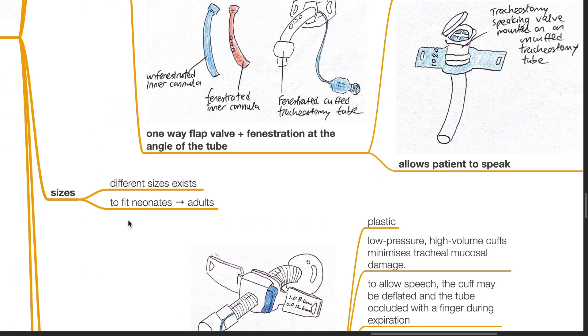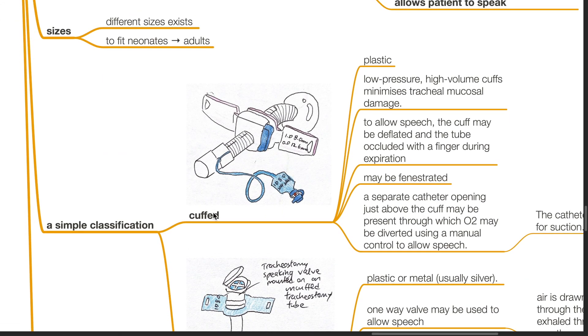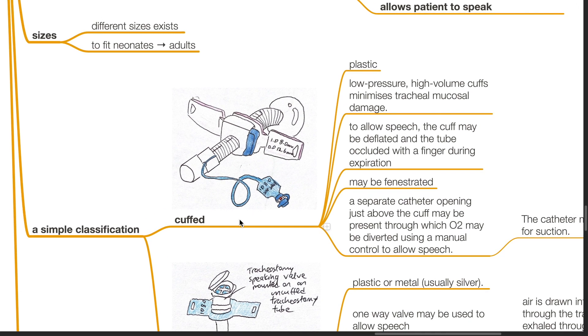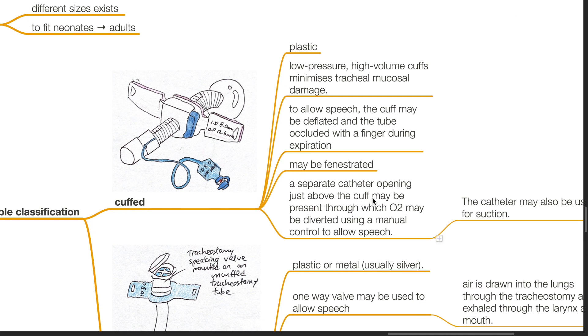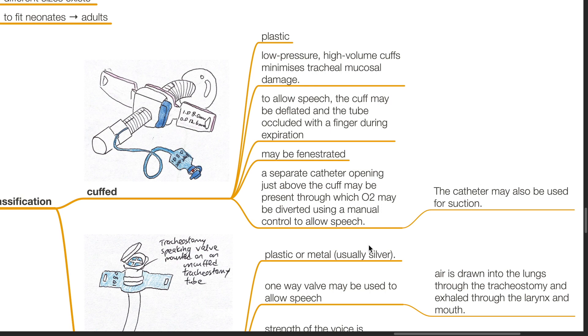Different sizes exist to fit neonates up to adults. A simple classification: cuffed and uncuffed. Cuffed tubes are plastic; low pressure, high volume cuffs minimize tracheal mucosal damage. The cuff may be deflated and the tube occluded with a finger during expiration to allow speech. Tubes may be fenestrated. A separate catheter opening just above the cuff may be present, through which oxygen may be diverted using a manual control to allow speech; the catheter may also be used for suction.